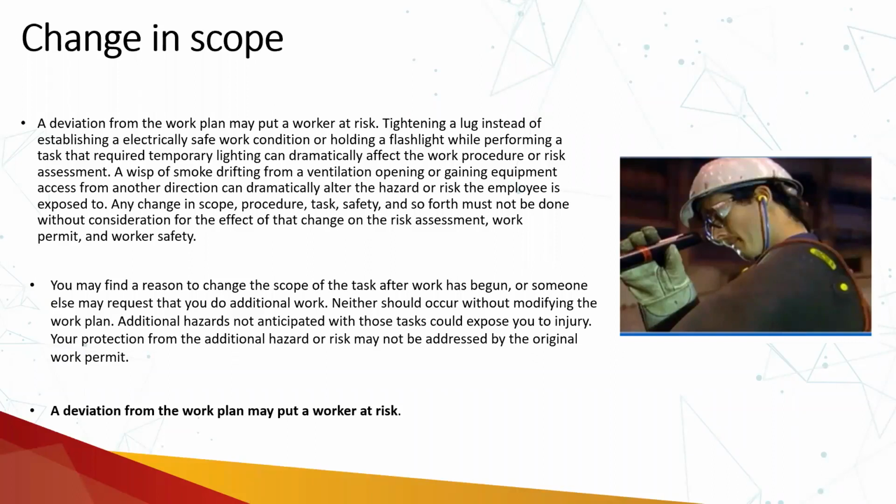So holding a torch in your right hand and performing the task will also fall under the scope change. Another type of scope change involves shifting from an inspection task to a maintenance, repair, or replace task. Those are well understood. But changing the environmental conditions or any other factor which can affect the safety of the employees and which requires job safety planning and briefing will also fall under the scope change.